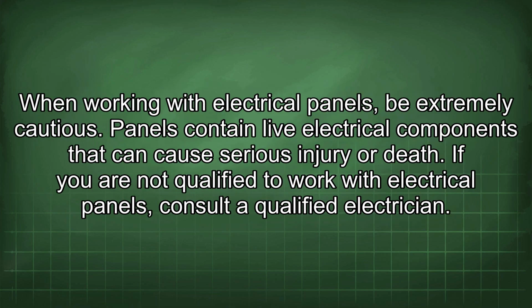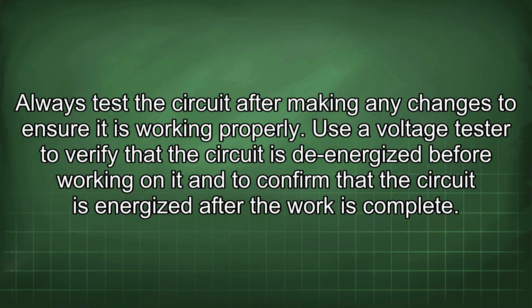When working with electrical panels, be extremely cautious. Panels contain live electrical components that can cause serious injury or death. If you are not qualified to work with electrical panels, consult a qualified electrician. Always test the circuit after making any changes to ensure it is working properly. Use a voltage tester to verify that the circuit is de-energized before working on it and to confirm that the circuit is energized after the work is complete.